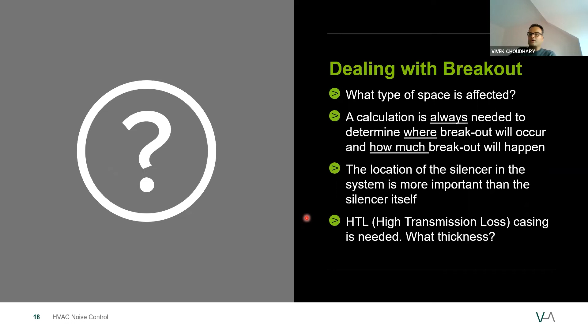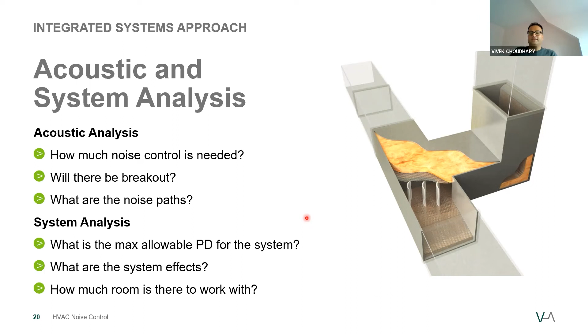Let's talk about the integrated system approach. So integrated system approach is a combination of acoustic analysis and a system analysis. So whenever anybody is looking into a project to make sure on the noise, especially the acoustical consultants, they focus on the acoustic sides of any project, which is how much noise control is needed, is there a breakout noise issue, and what are the different noise paths. And from a mechanical consultant point of view, we look into the maximum pressure drop allowed, the system effect, and how much room is there to work with. So basically what Vibro-Acoustics and Long Building will do is make a combination of both. So we provide a solution which not only works from the acoustics point of view, but also works from a system point of view as well, to make sure the solution will fit in the space and will not exceed the maximum pressure drop allowed.